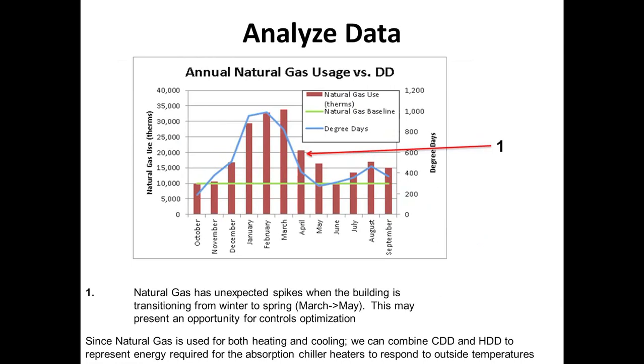Looking over at natural gas usage, in this case, we would normally look at heating degree days only, because this building just happened to use an absorption chiller, which uses natural gas for both heating and cooling. We actually combined our cooling degree days and heating degree days to just look at general degree days, which is the energy content expected to be used for the building based on outside temperatures. What's interesting here is we have the same kind of perhaps controls issues starting in March and traveling down to May, where energy consumption really spikes higher than expected based on outside temperatures. This just gives us a visual clue to explore this issue further and see how well the building's doing, and maybe there's a controls issue to explore.